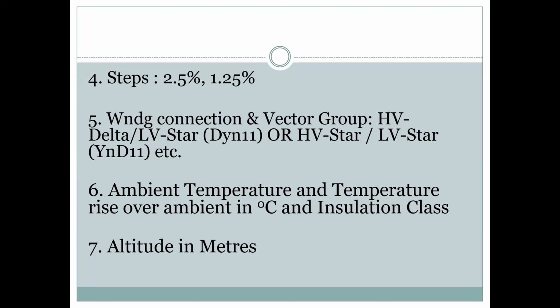Then ambient temperature, rise over the ambient temperature in degrees centigrade, insulation class, altitude. Altitude is also a main factor. We have supplied a transformer to Ladakh, where the ambient temperature goes down to minus 25 degrees centigrade, so you don't expect normal conditions. So we use a special type of oil. Normal oil is basically paraffin-based oil, and it gets limited cooling effect, not more than that. So we use naphtha-based oil. There is also a separate kind of oil prescribed for particular altitudes. Next.